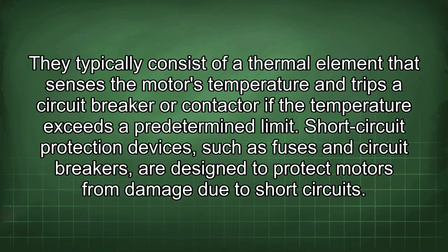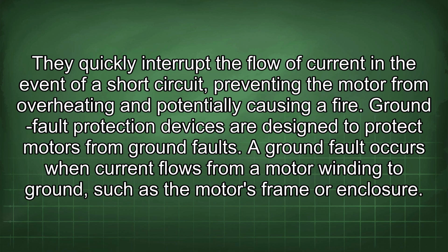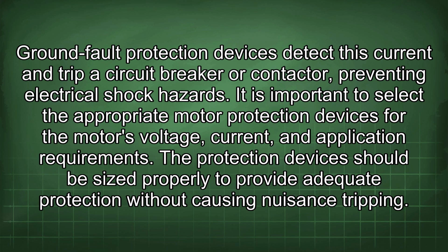Short circuit protection devices, such as fuses and circuit breakers, are designed to protect motors from damage due to short circuits. They quickly interrupt the flow of current in the event of a short circuit, preventing the motor from overheating and potentially causing a fire. Ground fault protection devices are designed to protect motors from ground faults. A ground fault occurs when current flows from a motor winding to ground, such as the motor's frame or enclosure. Ground fault protection devices detect this current and trip a circuit breaker or contactor, preventing electrical shock hazards.